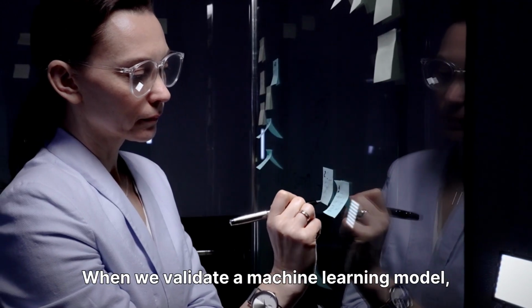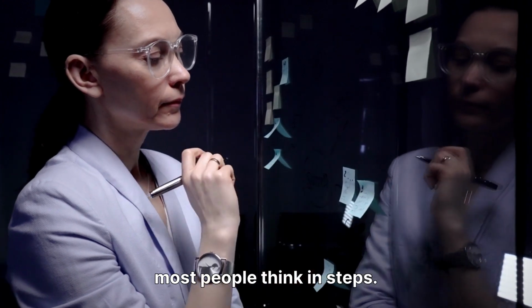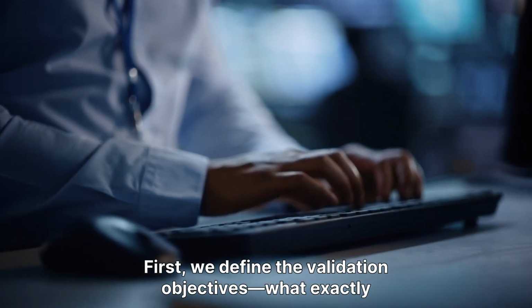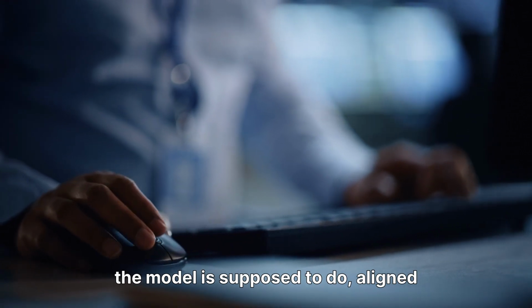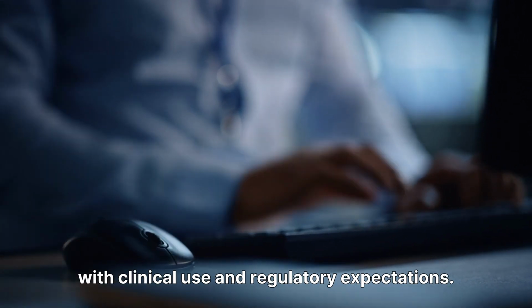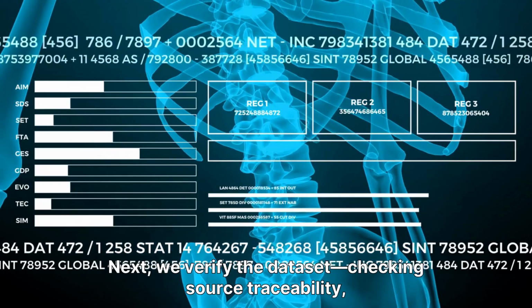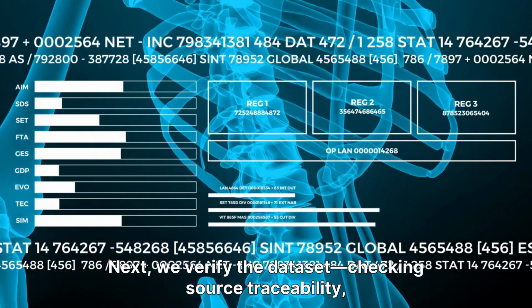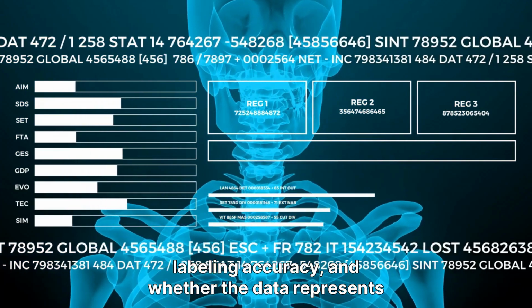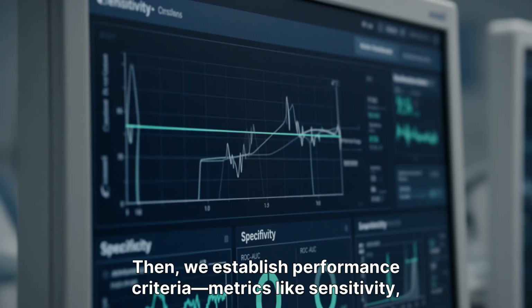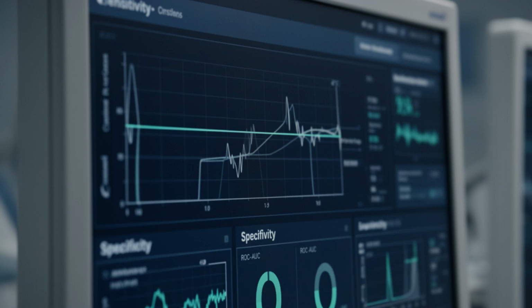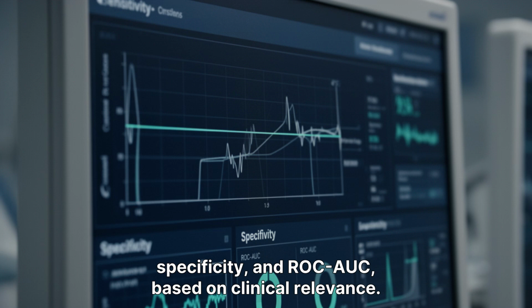Let's start simple. When we validate a machine learning model, most people think in steps. First, we define the validation objectives, what exactly the model is supposed to do, aligned with clinical use and regulatory expectations. Next, we verify the dataset, checking source traceability, labeling accuracy, and whether the data represents real-world scenarios. Then we establish performance criteria, metrics like sensitivity, specificity, and ROC/AUC based on clinical relevance.